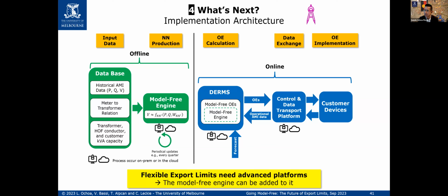Is there a way to see the section's conductor reaching the constraint? Well, just the head of the LV circuits can be checked, because we know the sizes of those conductors, and we can use it as a proxy. Why is it a proxy? Because when designing low voltage networks, and distribution networks in general, we do tapering, which means we start from a larger conductor to smaller and smaller, because we have fewer houses. So if the head part is okay, we can assume the rest is okay.